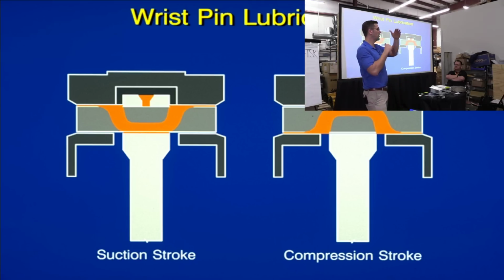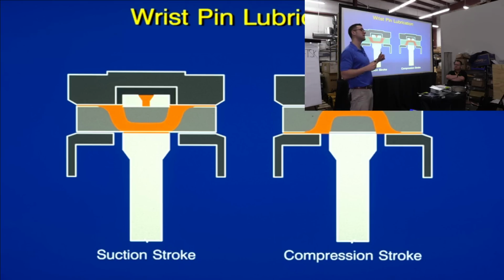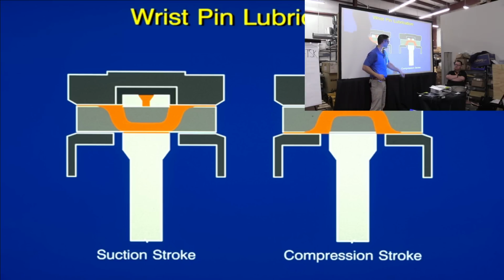So oil. You're working away and your compressor's running fine. You take that slug we just talked about, and you have discharge gas pushing down on here. What do you think's happening to this wrist pin? Do you think it's moving up and down like it should? It's always fighting, right? So you're not getting oil on both sides. You're getting oil here and then you get oil down here. Depending on the model of the compressor, there might be holes drilled through the rod. So now all of a sudden that discharge gas is pushing down on here and this is trying to push up. I'm not getting oil to my wrist pin.